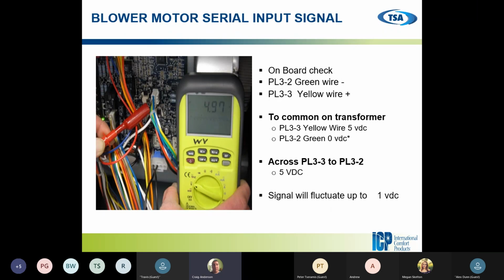So on our board now, we want to check our green, we want to check our yellow. This is our input signal from the board. Again, we want to check from common to our yellow. We want to check common to green. We want to check ground to green. We want to check ground to yellow. Make sure our voltages are steady and staying the same on both. And then we want to check them across. Yellow to green, 5 volts DC. You might get a little bit of fluctuation, but it'll be a little bit under, but it should be quite steady. It shouldn't be jumping around.